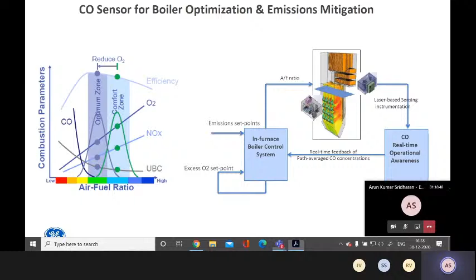We actually demonstrated a CO-only version of the fast emission sensor at a GE test boiler facility, and showed that the results compared very well to the reference sensors on the site. So that's one thing that we have done in terms of using sensors for the optimization of boilers for coal power plants. Another project that we did to help coal plants operate more flexibly involved what we call ignition technologies. If you go to slide 24, what you will see is oil burners. Because there's so much renewable power in the grid, you need to operate coal power plants at lower and lower loads.